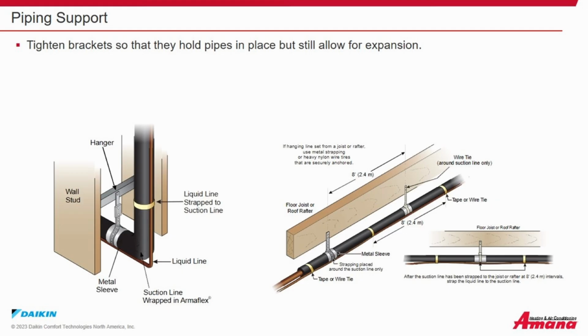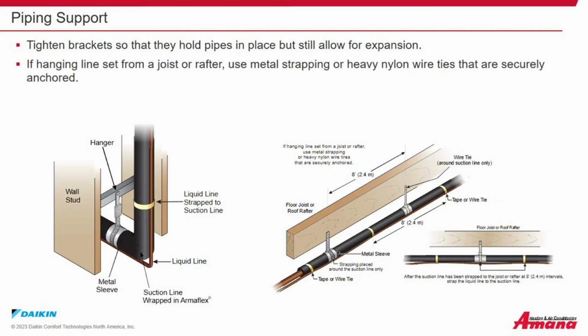Piping support. Tighten brackets so they hold pipes in place but still allow for expansion. If you're hanging a line set from a joist or rafter, use metal strapping or heavy nylon wire ties that are securely anchored.